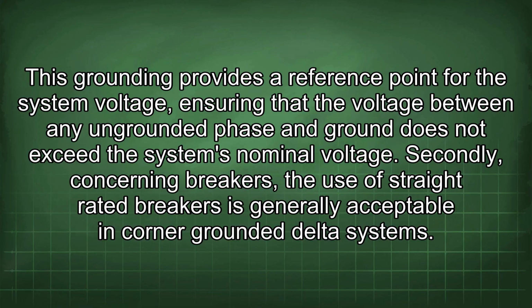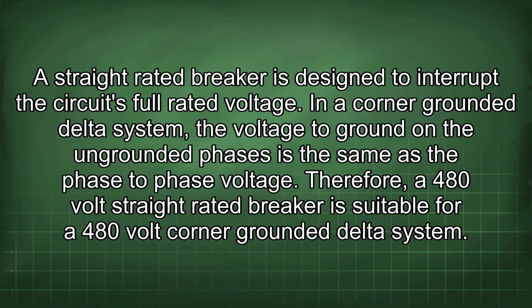Secondly, concerning breakers, the use of straight-rated breakers is generally acceptable in corner-grounded delta systems. A straight-rated breaker is designed to interrupt the circuit's full rated voltage. In a corner-grounded delta system, the voltage to ground in the ungrounded phases is the same as the phase-to-phase voltage. Therefore, a 480-volt straight-rated breaker is suitable for a 480-volt corner-grounded delta system.